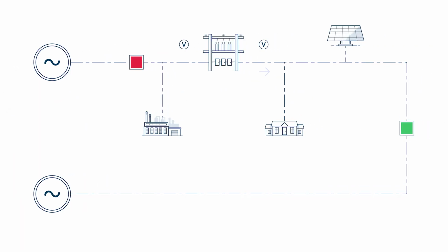Here, we see a reverse direction power flow. The Flex DG algorithm verifies that voltage regulation is working properly, so the control keeps the regulator tapping in its original direction. Now, power is flowing in a reverse direction again.